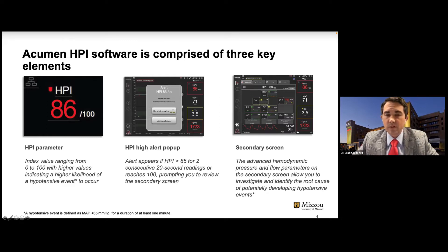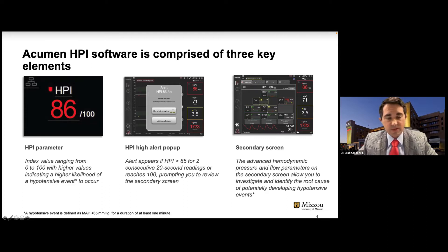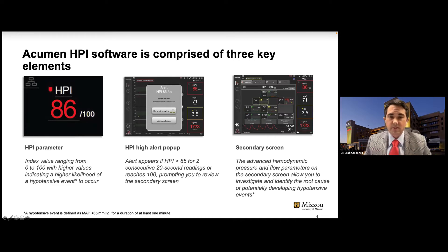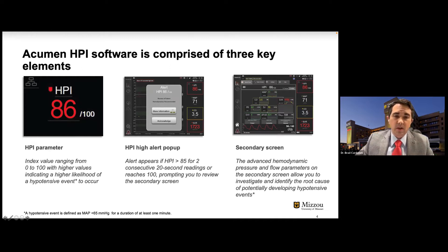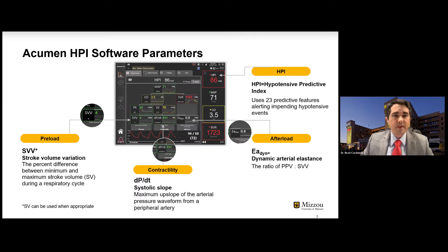You can also get an HPI high pop-up alert showing that you're likely to become hypotensive when the number reaches greater than 85 for two consecutive readings. This is very real-time — each reading occurs in 20-second intervals. These parameters give you real-time information and feedback to treat the individual patient in the OR or ICU. We get a secondary screen that gives us information about why the patient is truly hypotensive or whether we're compromising flow, which is very important.